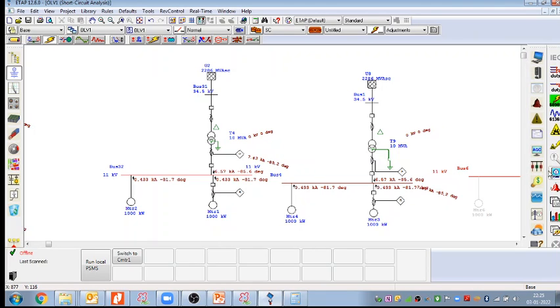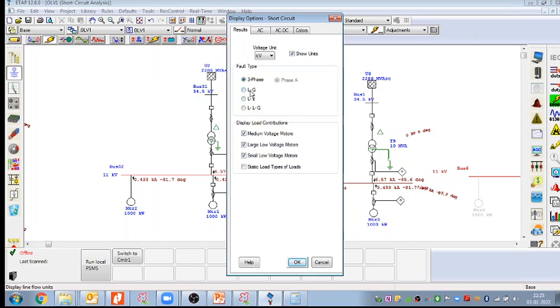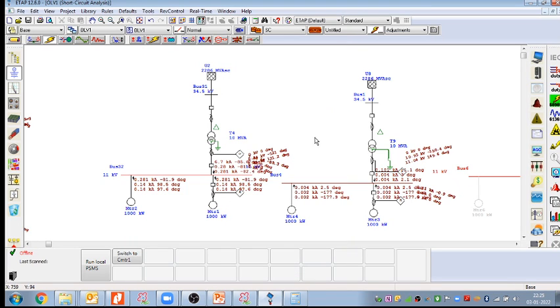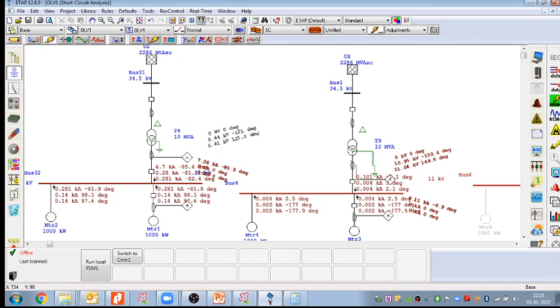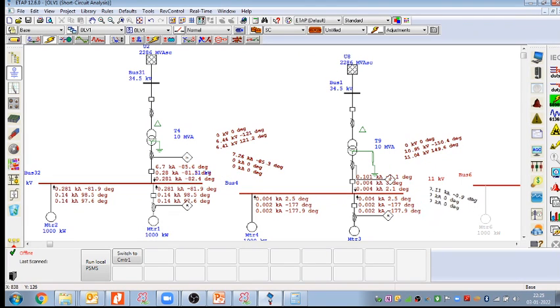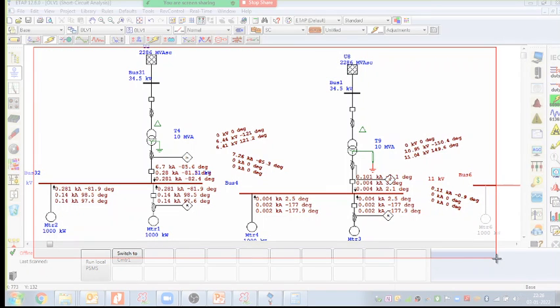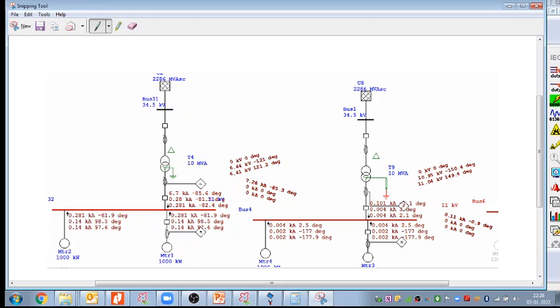Okay, just give me 1 second. 60909 and 3-phase fault. Let me go to the line to ground fault and take the phase value, ABC value, R, Y, B phase. I just wanted to take all the 3 phases in a common picture. Let us do a comparison between these two types of grounding, solid grounding and NGR grounding, and let us build some concept from here. Let me take the snip from here with the snipping tool, and I select it here and I can do the comparison now.